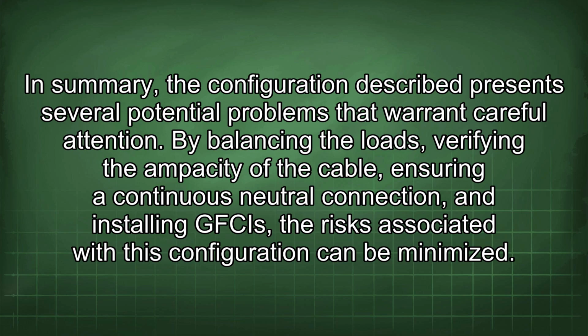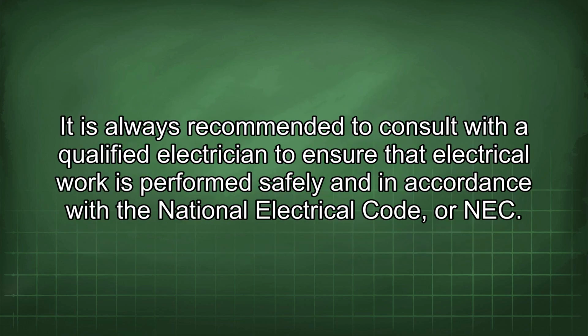In summary, the configuration described presents several potential problems that warrant careful attention. By balancing the loads, verifying the ampacity of the cable, ensuring a continuous neutral connection, and installing GFCIs, the risks associated with this configuration can be minimized. It is always recommended to consult with a qualified electrician to ensure that electrical work is performed safely and in accordance with the National Electrical Code, or NEC.